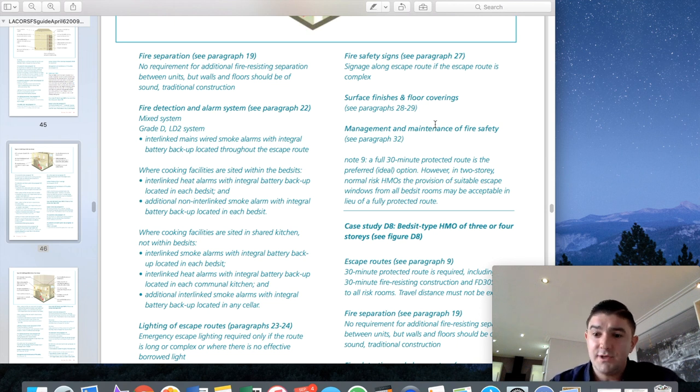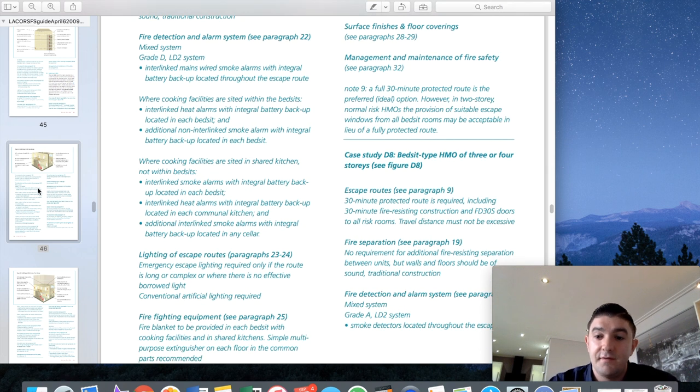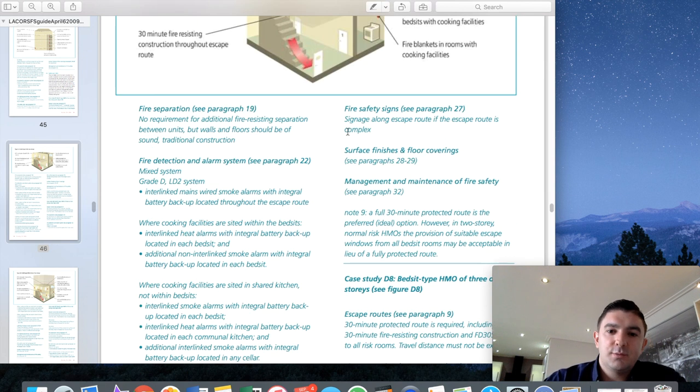So what we do at VCC Homes is that I go around and do a communal area inspection and external inspection, and I'll detail all of this in a report, as well as the fire safety logbook that I do, which tests the emergency lighting, the fire alarms, and all that sort of stuff. I tick again on both documents that I've checked the fire routes and everything's working as it should be. Yeah, and checking fire blankets and all that sort of stuff, and the emergency lighting, which I've covered. So yeah, that's within this book.